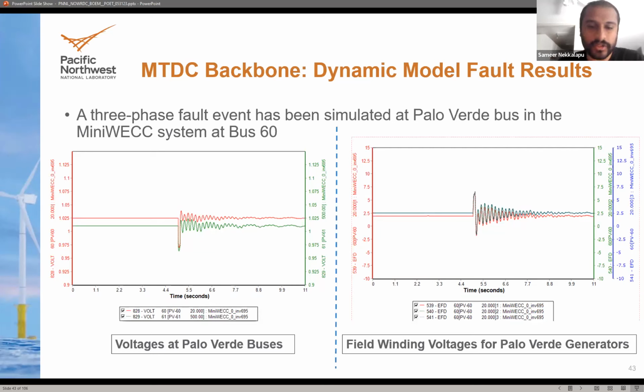Once we had all this modeling capability, we ran some tests such as a fault at Palo Verde bus to benchmark the model. In this result, when we ran a three-phase fault with some fault resistance, not a bolted three-phase fault, the system response is pretty stable, and the field winding voltages respond accordingly. As the voltage drops at its terminals, the field winding increases to compensate. So the response is pretty good.